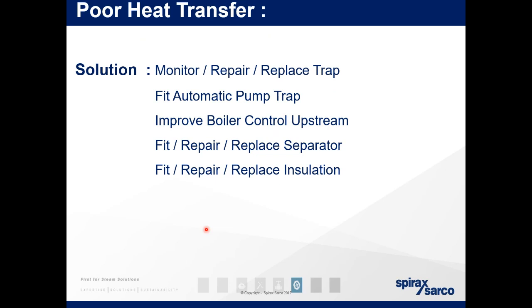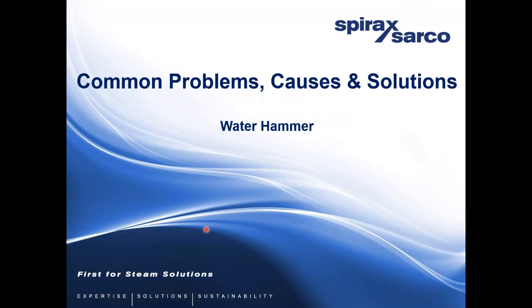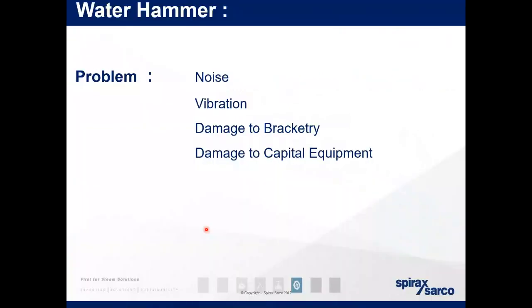Okay. So water hammer. So the problems: how do we recognize water hammer in our systems? You have noise, you have vibrations, you have damage to bracketry, so maybe brackets breaking that are supporting pipes, and damage to capital equipment, so effectively damage to control valves, damage to traps. Many of you may have heard the banging you hear on a water pipe. That's water hammer.